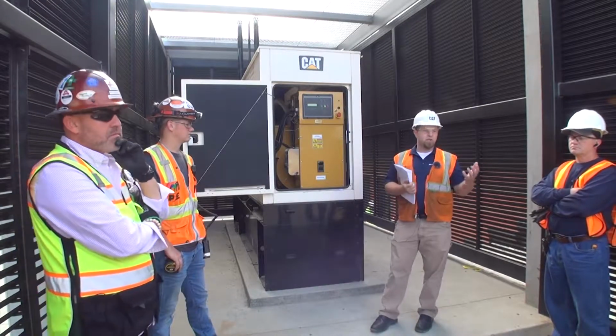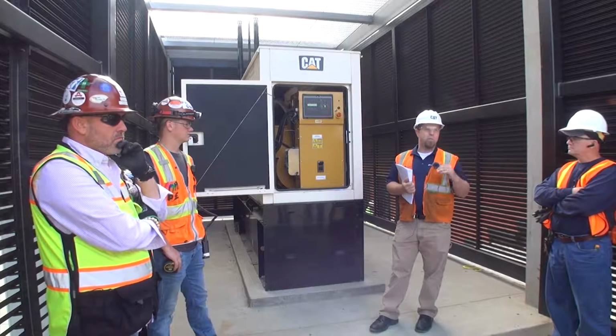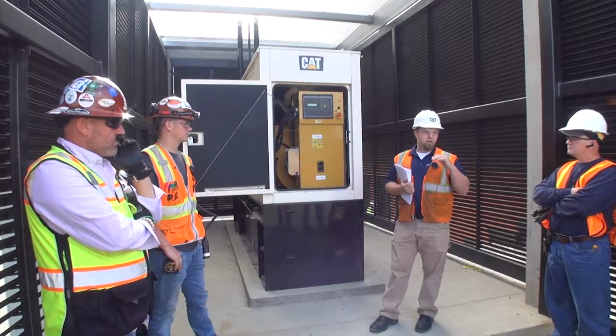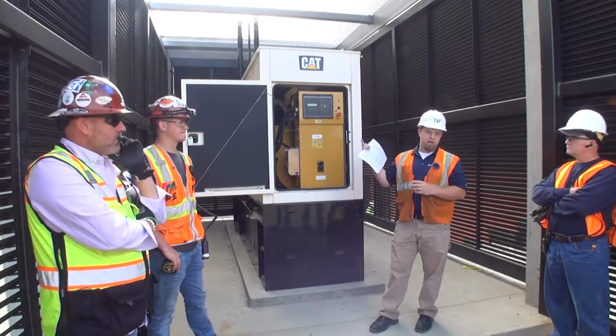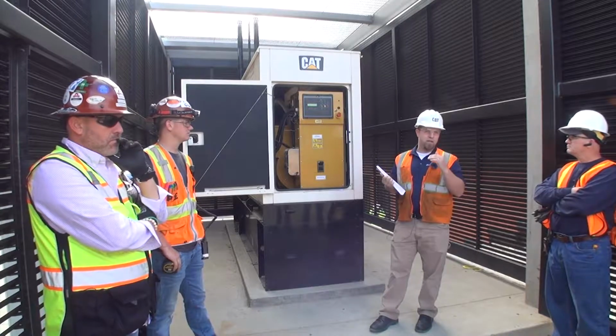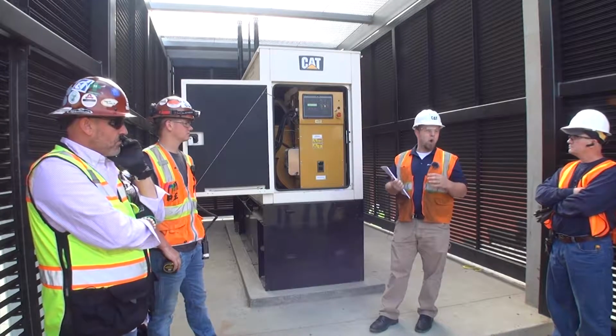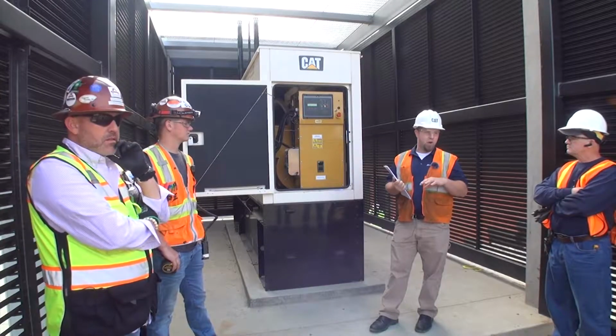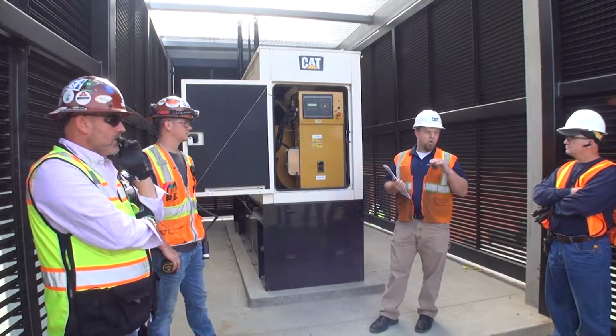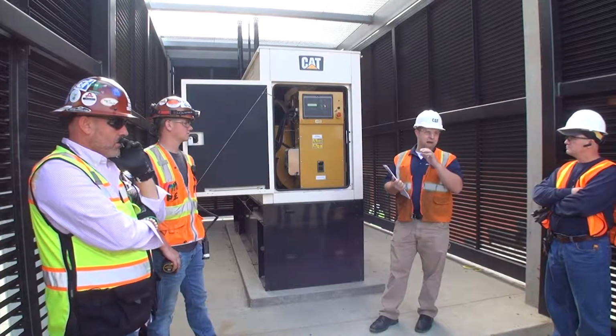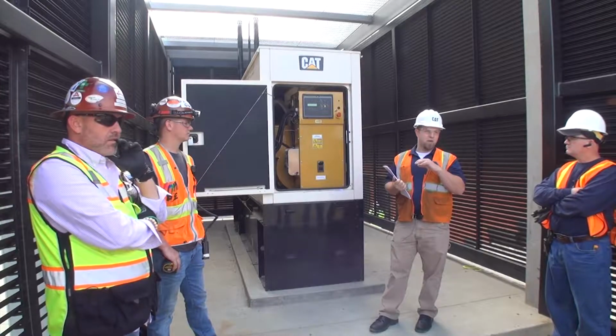When you do your monthly transfers, if you are not above 30% load—I'll show you how to look at your kilowatts and load percentage—then once a year you are required to do a 1.5 hour load bank: half an hour at 50% load and the last hour at 75% load or more.